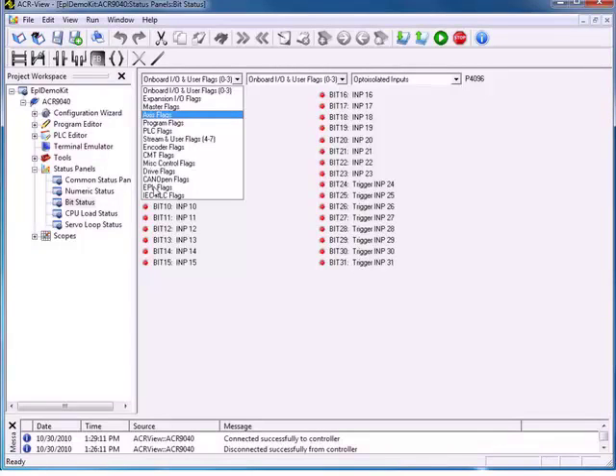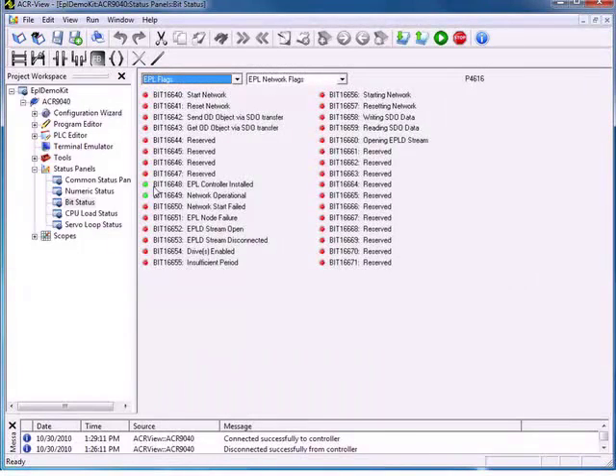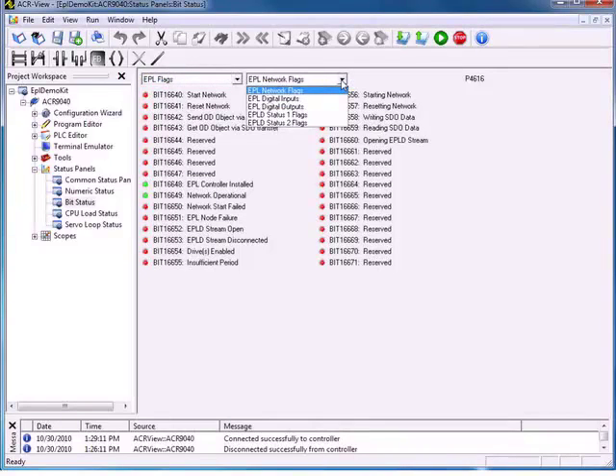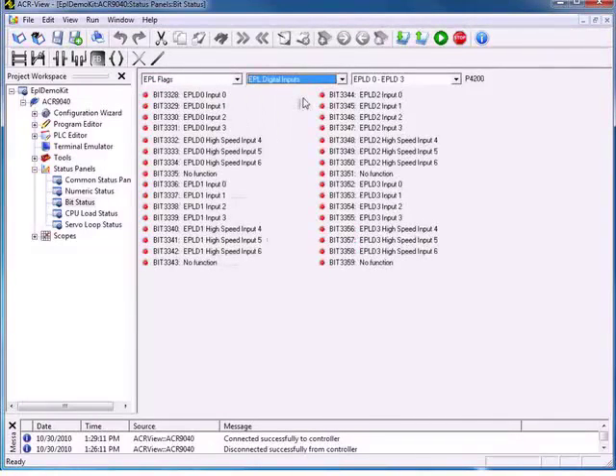I want to look at the onboard IO, so I'm going to take a look under the subcategory at my digital inputs. Now if I press buttons on our demo unit here, we can see that I'm pressing input 1, pressing input 2. So we can test our installation from here. I can take a look and see if my outputs are turned on, and if I'm having trouble on the machine, I can determine whether or not I'm actually turning it on, or if it's some other problem.